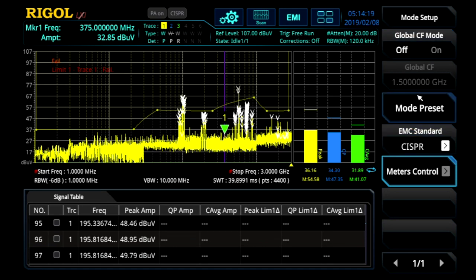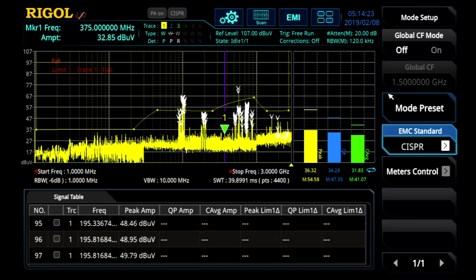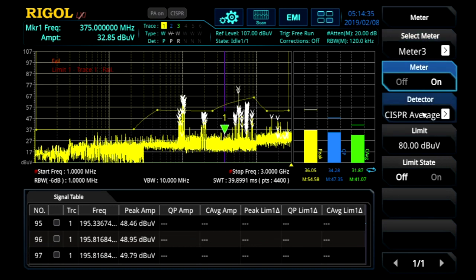Here in the mode setup is one of the first areas we look. You can set CISPR or the regular detectors. Here you can also configure the meters. We've pre-configured them for a peak detector, a quasi-peak detector, and a CISPR average detector. That gives us the ability to look at three different ways these signals might appear in an actual compliance test.